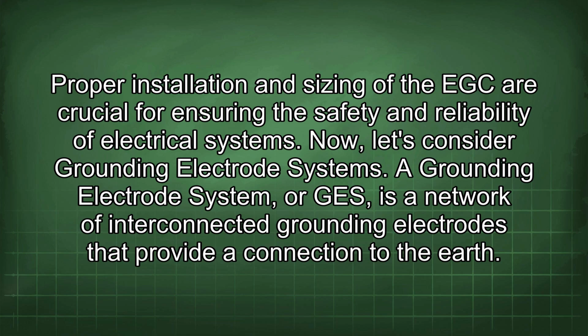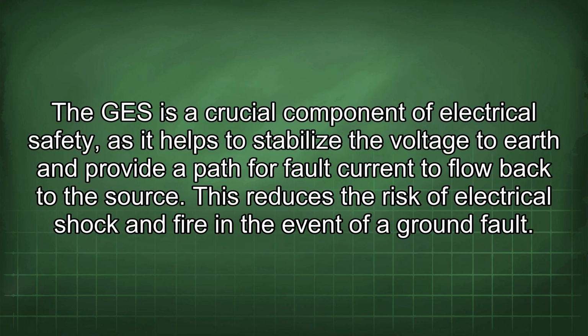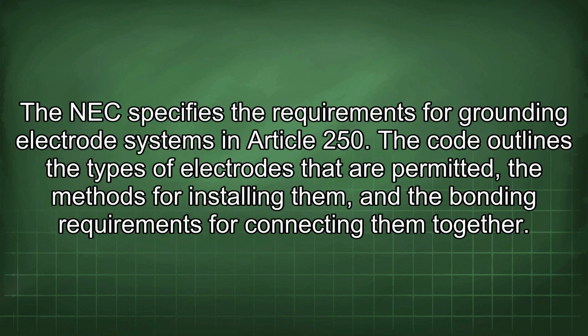A grounding electrode system, or GES, is a network of interconnected grounding electrodes that provide a connection to the earth. The GES is a crucial component of electrical safety as it helps to stabilize the voltage to earth and provide a path for fault current to flow back to the source. This reduces the risk of electrical shock and fire in the event of a ground fault. The NEC specifies the requirements for grounding electrode systems in Article 250. The code outlines the types of electrodes that are permitted, the methods for installing them, and the bonding requirements for connecting them together.